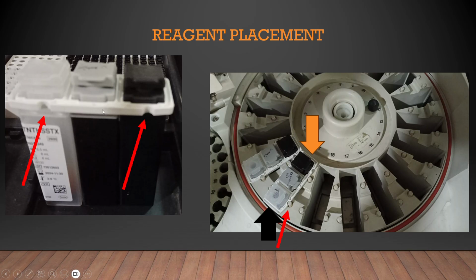Now the common mistake which many laboratory technicians make, or take for granted, is they open this cap and then try to place it inside this. Please don't do this. Okay, what you should do, when you are taking it out from the refrigerator, make sure that the caps are properly closed. Keep it in its rack and then loosen the caps. So when you are putting the reagent into this E411 reagent disc, you have to loosen these caps, because the instrument will open the cap and close the cap by itself. It has a mechanism to do that.